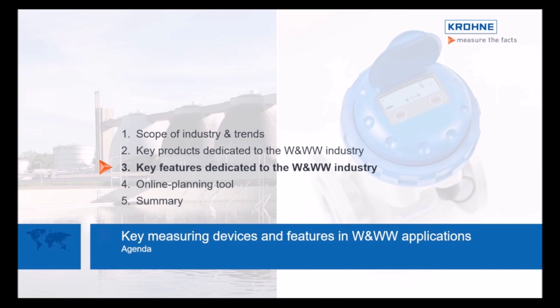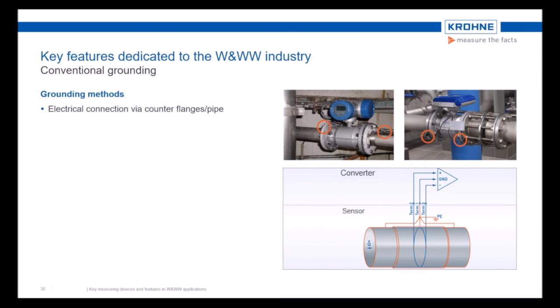Based on the presented key products, we are now heading to some dedicated key features to look into with a deeper focus. First of all, we start to compare the most common grounding methods which are required when operating a MAG meter. Due to the measuring principle, it is mandatory to have a potential-free condition before and after the meter to only grab the voltage which was induced within the magnetic field within the meter.